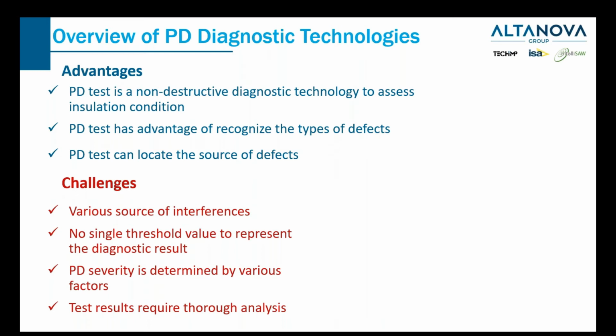We need to consider what type of discharge we're talking about, where the discharge site is, and what the tolerance of the equipment for PD is. A motor is a great example, right? Mica insulation has a much larger tolerance for PD activity, but for organic insulation, the tolerance for PD is not even close. So that brings the last challenge: the testing result is complicated. It requires experience and a thorough analysis to derive the useful information.